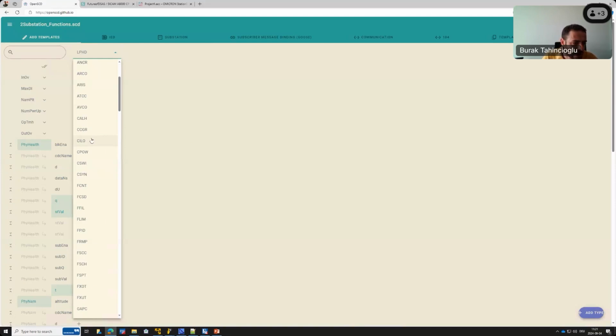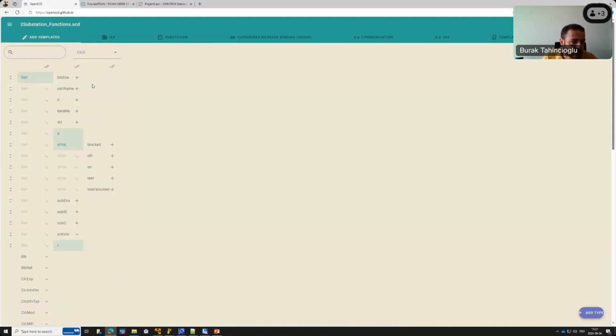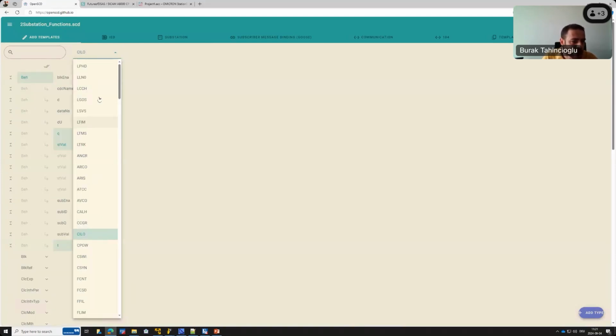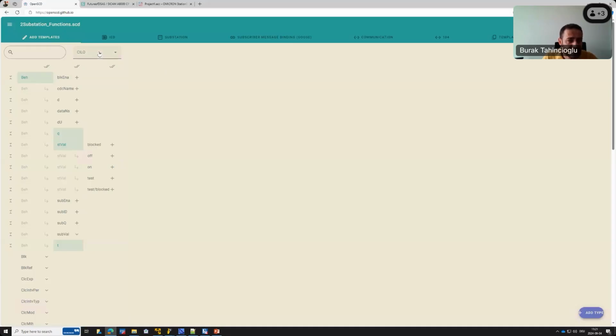For instance, I can show you the simple example of XCBR/CILO. In the drop-down list, you see all the logical nodes defined in the standard. At this point, it's better to have the standard with you, parts 7-3 and 7-4, because here you need to decide. We defined the CILO — what was that? The control interlocking. For defining interlocking, you will see different levels.